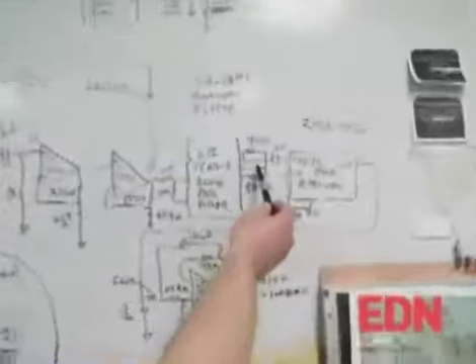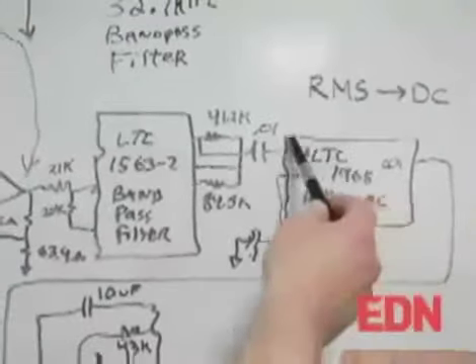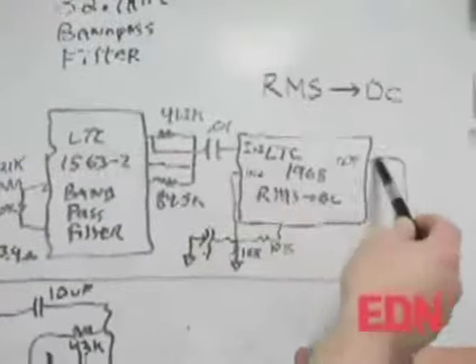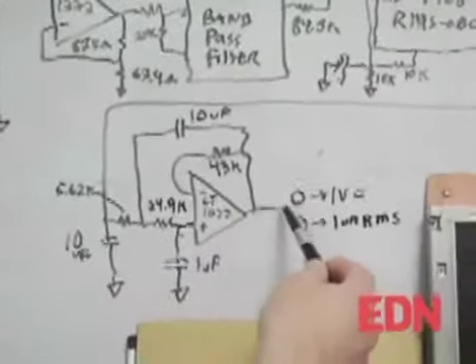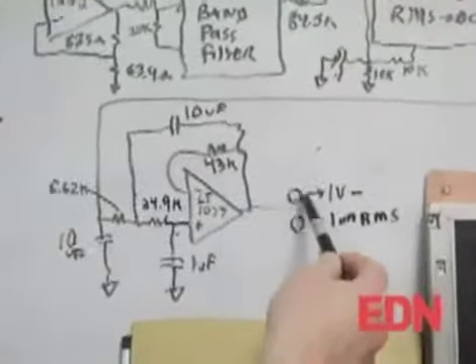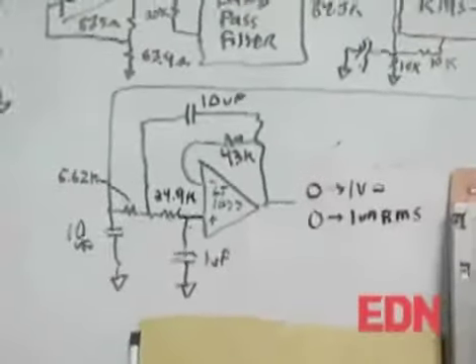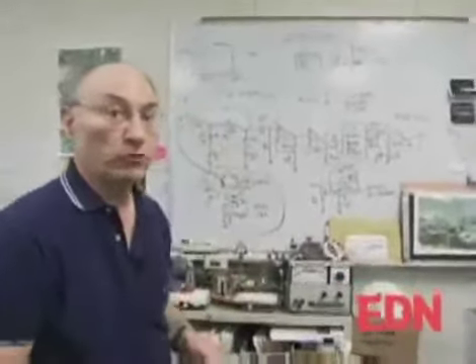Once we come out of the bandpass filter, we run into an RMS to DC converter to get the RMS value of the signal. That drops out of this last amplifier with a scale factor of 0 to 1 volt equals 0 to 1 microamp RMS. We're shooting for an overall accuracy of 3 or 4% in the measurement.